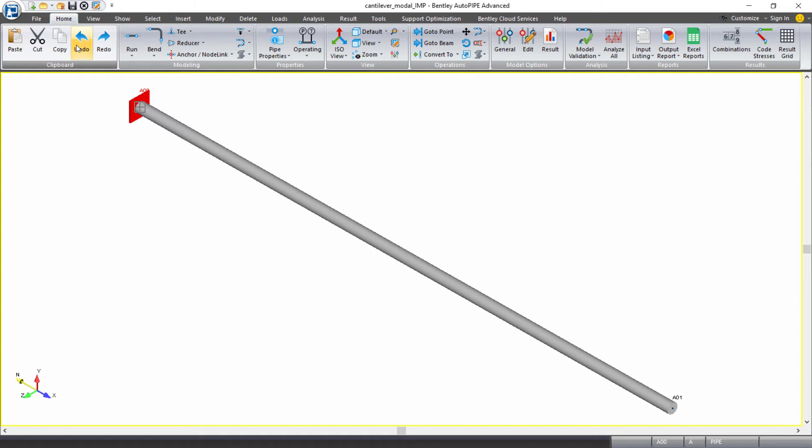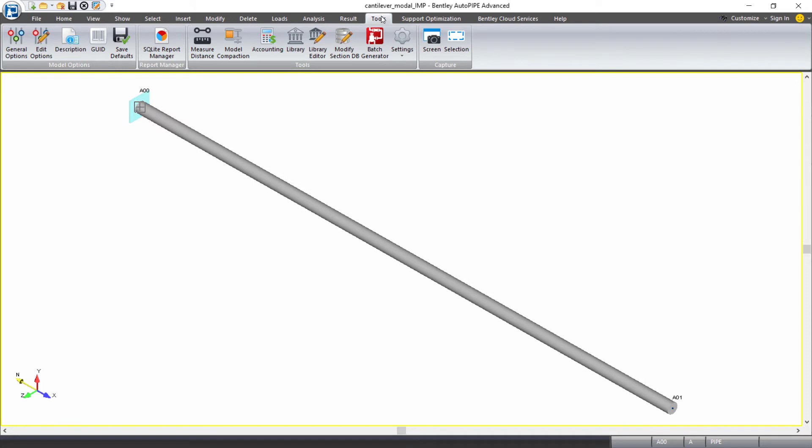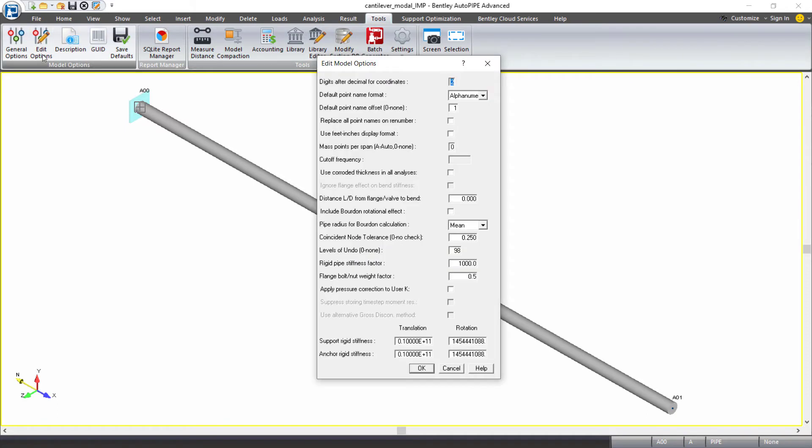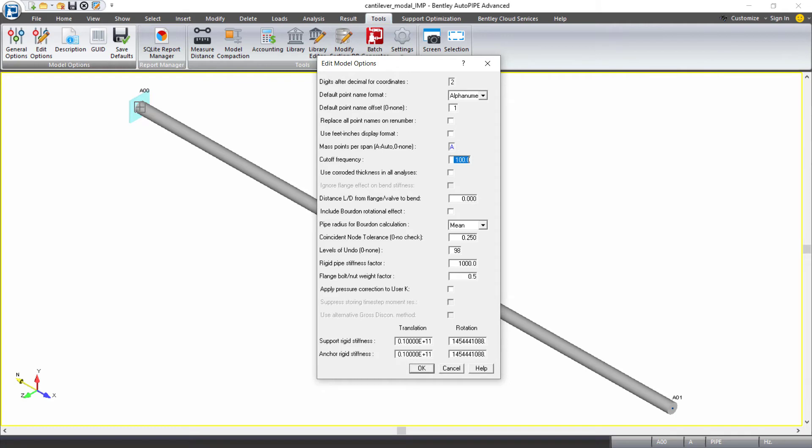Now I want AutoPIPE to automatically add in some additional points for me along this pipe. I can do that by coming up to tools ribbon tab. Under model options, I'll select edit options. In the mass points per span input, I will input A for automatic. Remember, this will use Roark's equation. And when I press tab, we have to input a cutoff frequency to be used in that equation. So we'll enter 100 Hz. And then I will click OK.